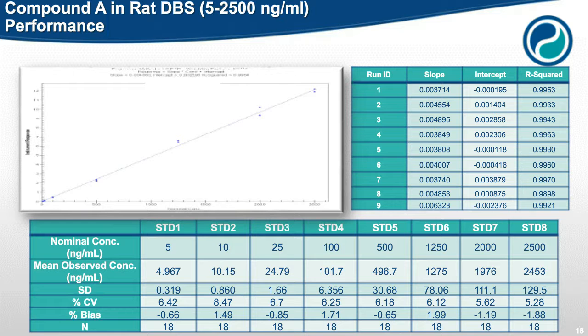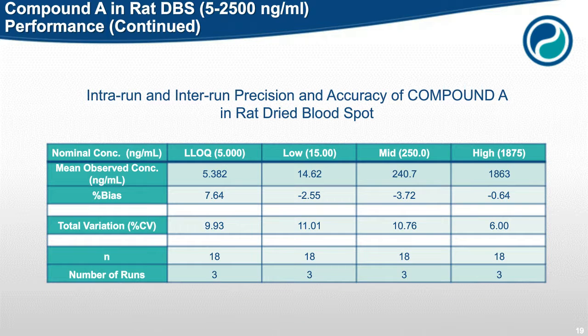This slide shows you the result from the 3 intra runs. So all 4 levels of QCs passed. There's not a single failed QC. Accuracy and precision are good.